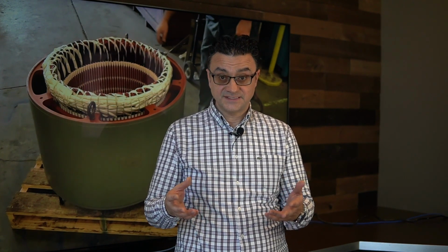So examples of failure modes are bad bearings, rotor bar degradation on your motors, intermittent ground fault problems we can see and capture and alert. We can see mechanical load degradation on a number of different devices, whether it's gearboxes or fans.